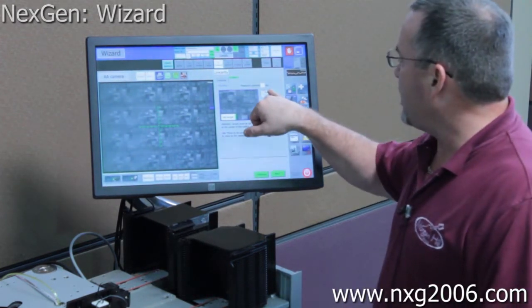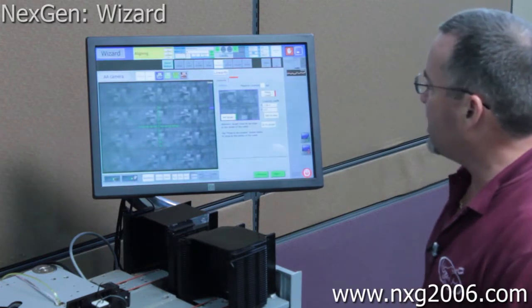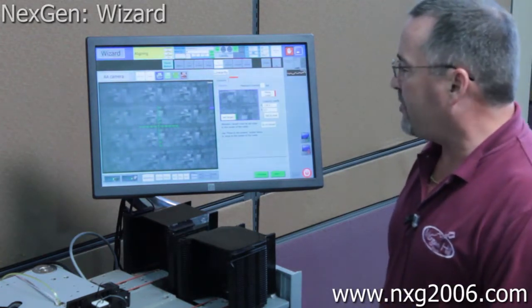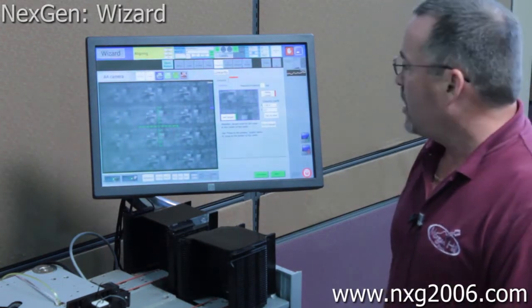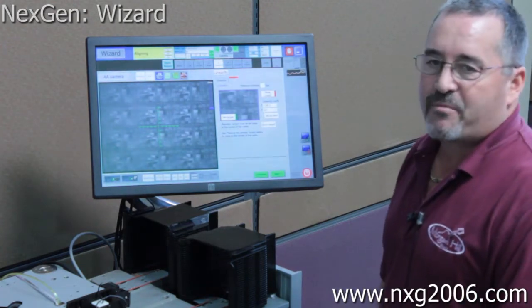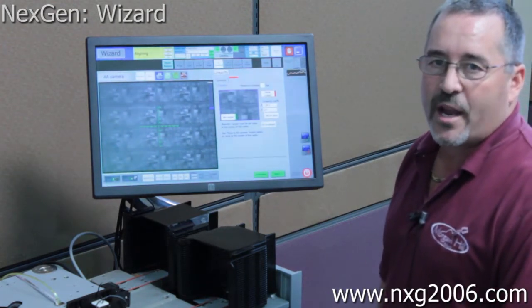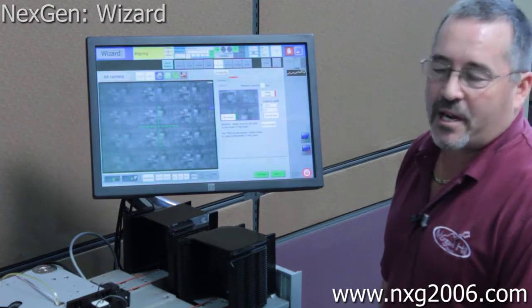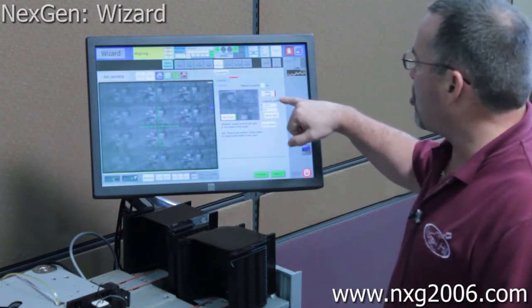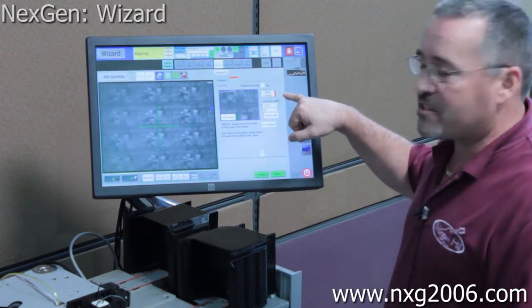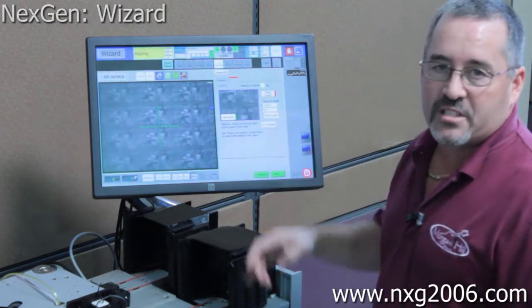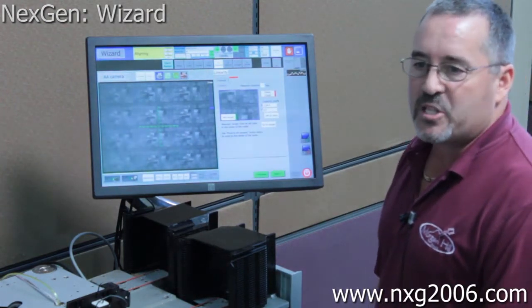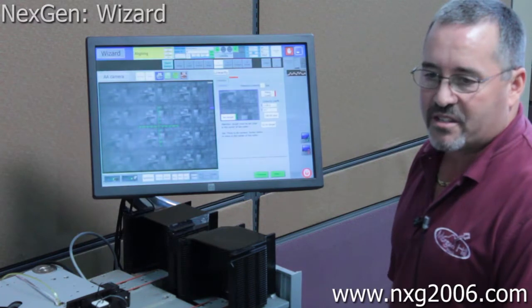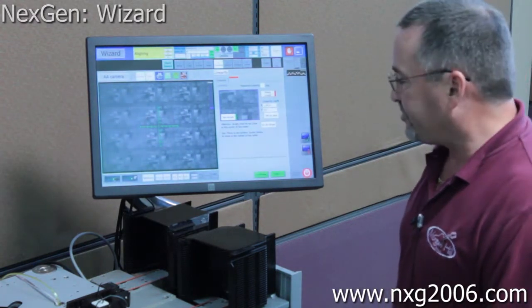So at this point we're going to make linear, and what it's going to do is it's going to step left in the X direction first and then the Y, using the die size that's entered in there. Now I purposely entered in wrong numbers so it would have to make some corrections. And those numbers are going to show up here under the linearity coefficients. Obviously in a perfect world it's going to be close to 0. Typically speaking, most probers are going to have some offset because of thermal expansion.